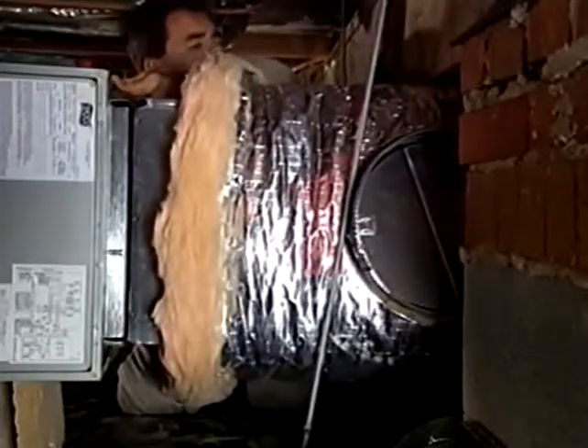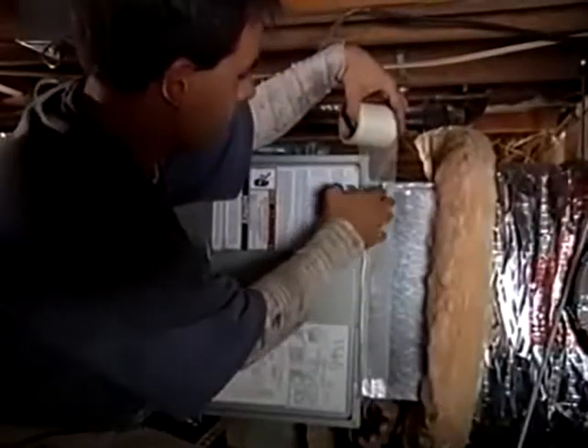Okay, put this side here first. When making the plenum connection to the air handler, taking extra care to seal this connection is extremely important. Okay, push in a little bit more. It is here that much of the air leakage can take place. Proper technique starts from the moment the connection is made. You can see these small gaps at the corners can be potential sources of air leaks. This contractor first seals these small gaps with a UL 181 foil tape. He then uses a fiberglass mesh tape around the entire connection. Finally, he paints this surface with mastic.